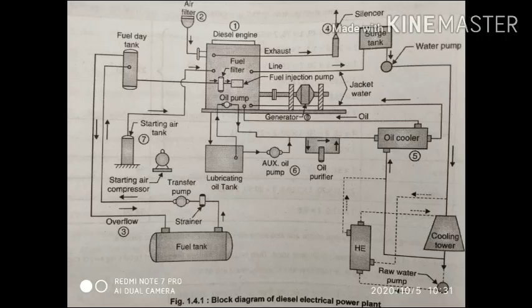The air filters are provided to remove dust and other suspended impurities from the air to be supplied to the engine. The supercharger is usually employed to increase the pressure of intake air above atmospheric in order to develop an increased power output. The air is drawn from outside the engine room and delivered to the inlet manifold through ducts or pipes and filters.